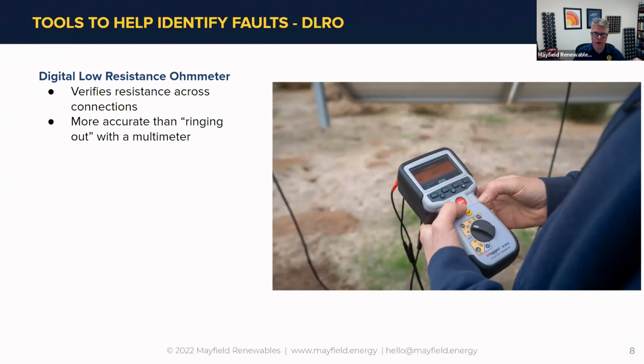So they do have to pass current through and measure the resistance, and the resistance has to be a tenth of an ohm or less. So 0.1 ohms or less is the threshold.